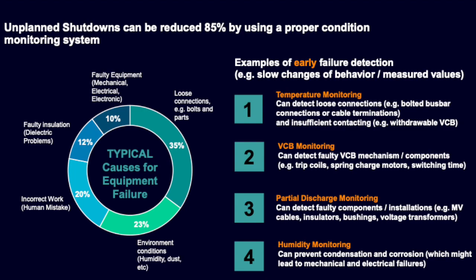These possible failures can be detected earlier by different possibilities. One part of the condition monitoring is temperature monitoring, which can detect loose connections and insufficient contact pressure and/or surface area.